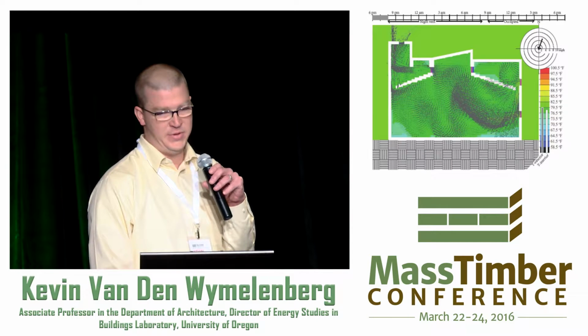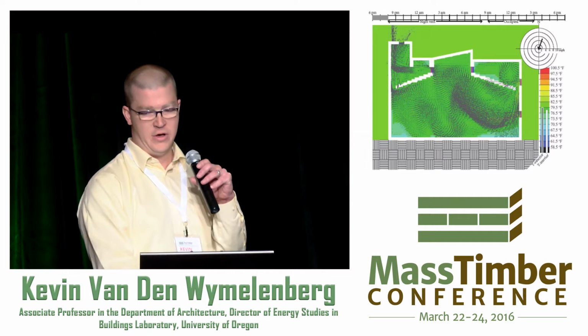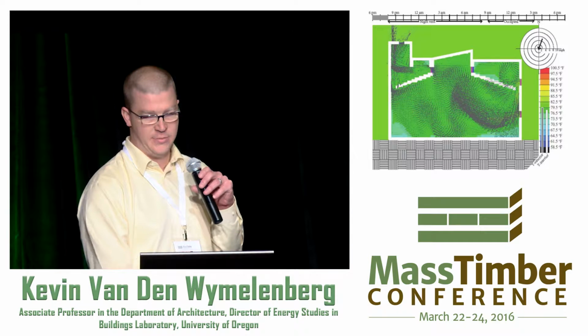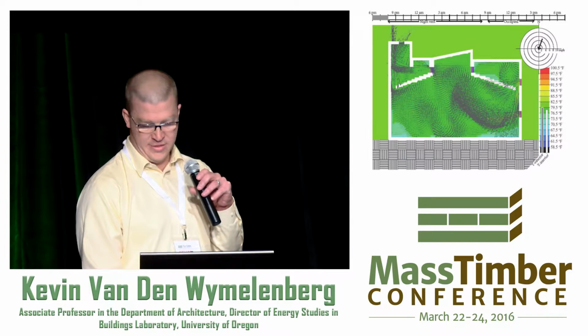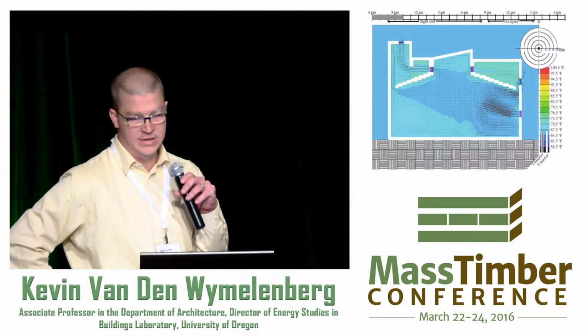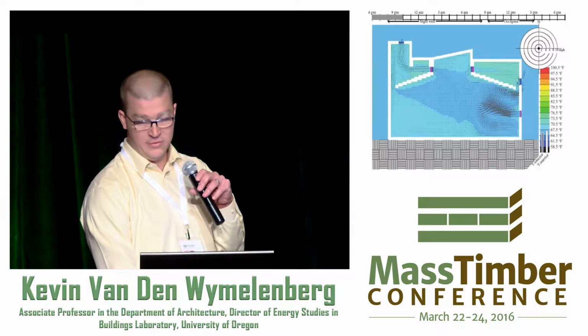So what we're looking at is a peak cooling design day here at 9 p.m., where we've opened up all those inlets and we're letting fresh air from outdoors in through these lower and upper windows and driving it out the turbine. Whether there's wind or not, it works because we're relying on stack effect. So even here with no wind at 10 p.m., we're still getting cooling effect, and that interior temperature has really dropped down.